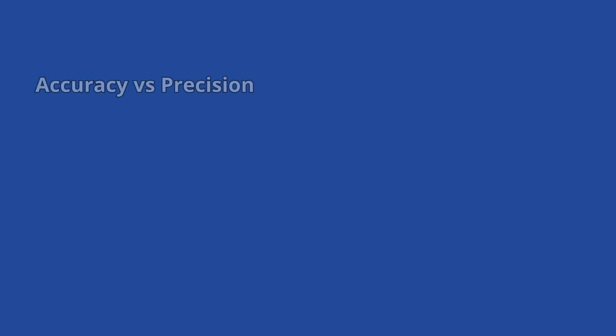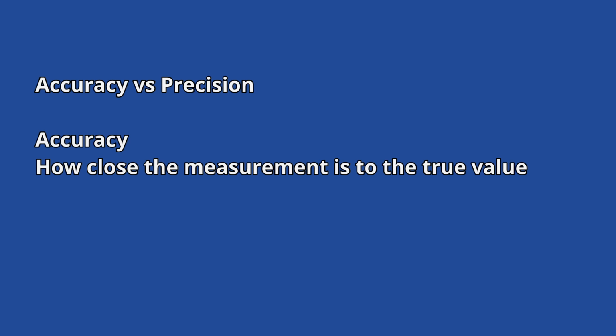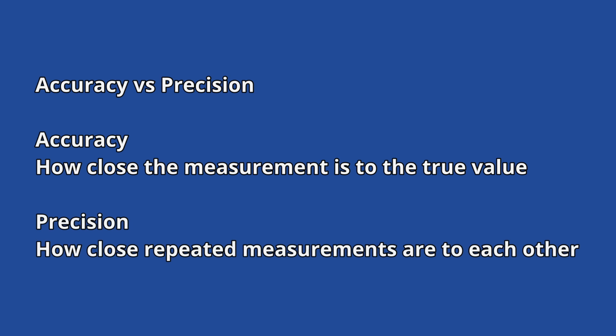An element of frequent confusion is the difference between precision and accuracy. As I stated earlier, accuracy refers to how close a measurement is to the true value. Precision, on the other hand, refers to how closely repeated measurements of the same input are to each other. We expect that when manufacturers provide specifications, they are indicating how well the meter is at measuring the true value. While we can't assess the true accuracy of a meter without comparing to a known reference, we expect that the meter was calibrated during the manufacturing process. A meter that produces highly consistent measurements that are a long way from the true value would be of little use to us.